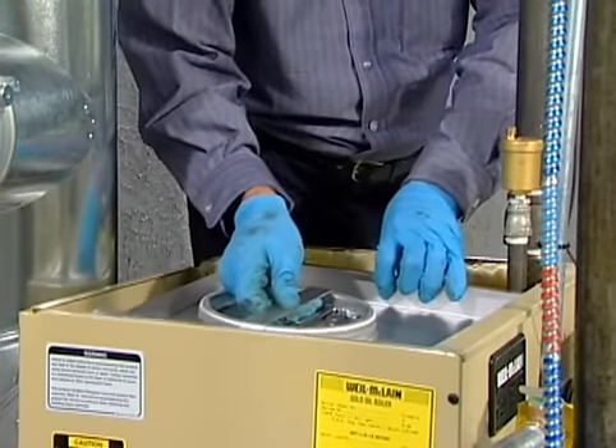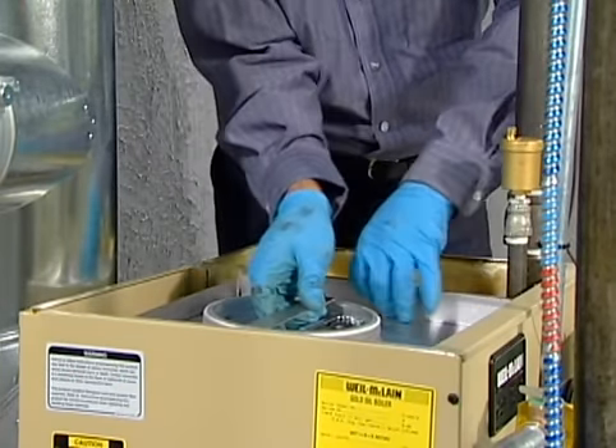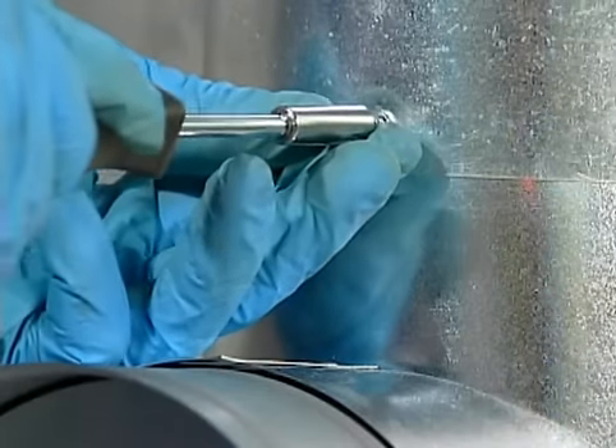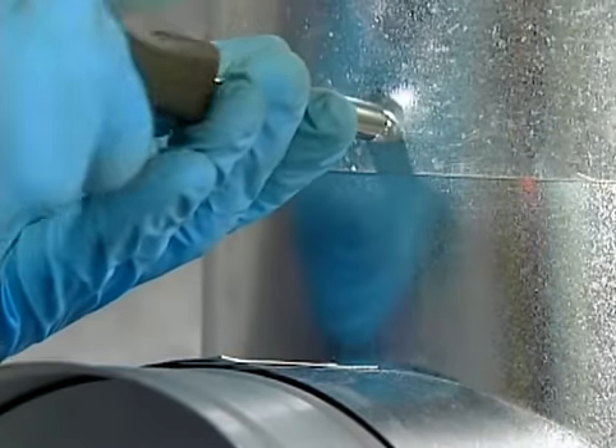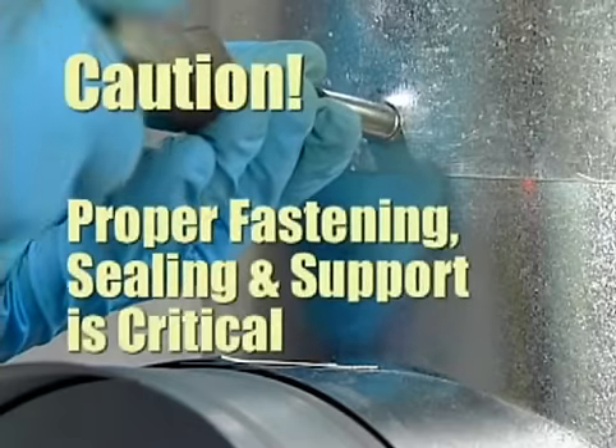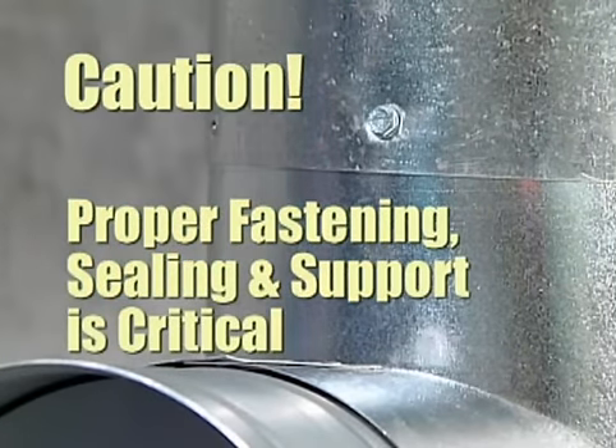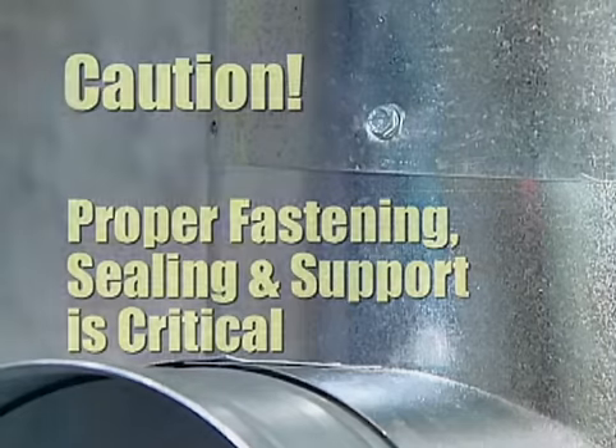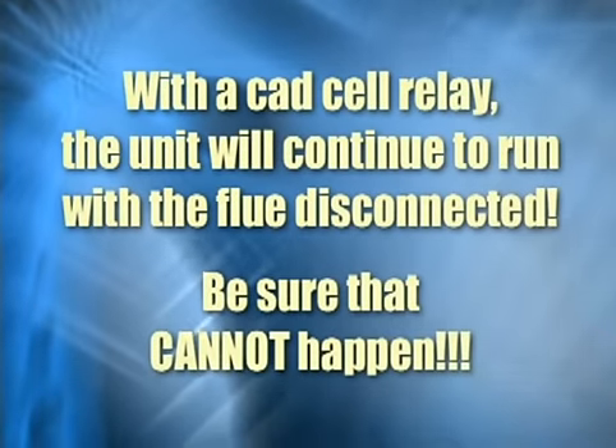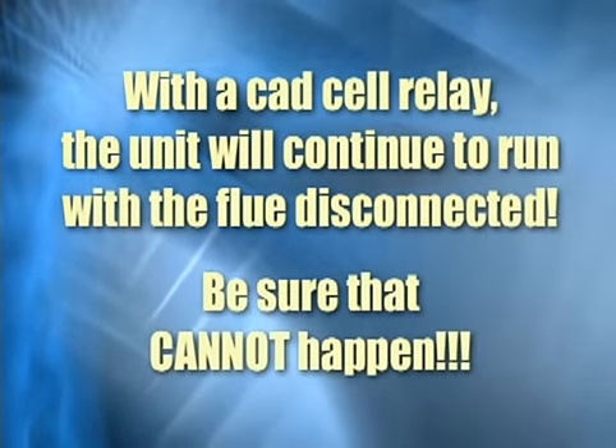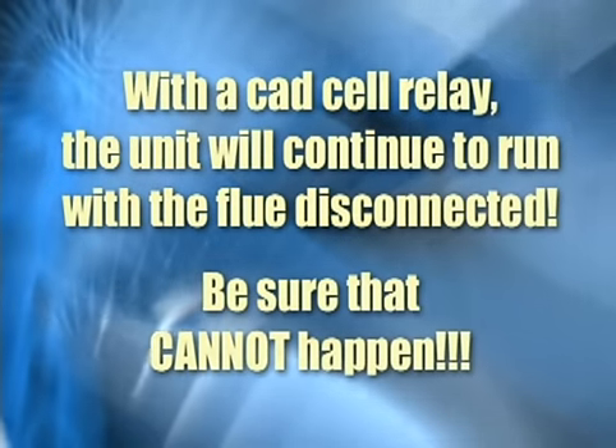Reassemble the unit using furnace cement if necessary to seal any air leaks. Double check to be sure the flue pipe is connected with sheet metal screws and supported. Proper fastening, sealing, and supporting of flue pipes is critical. With a CAD cell relay, the unit will continue to run with the flue disconnected. Be sure that cannot happen.